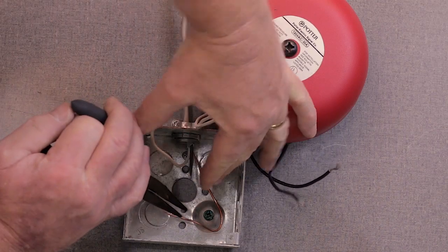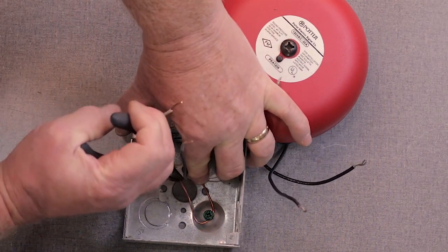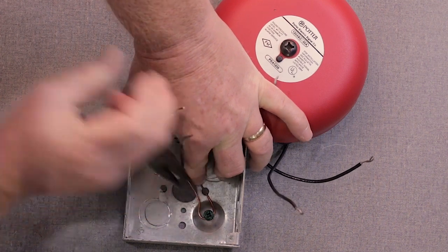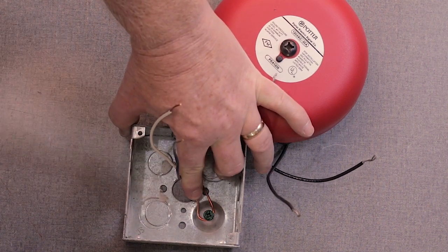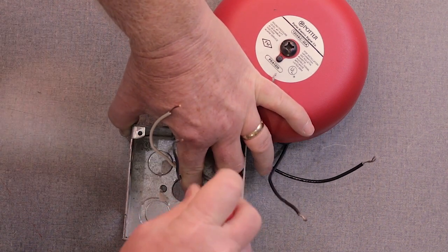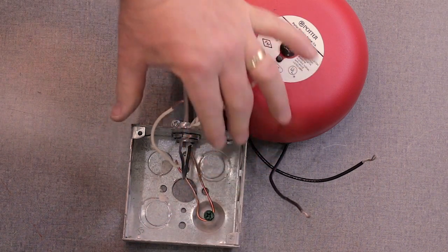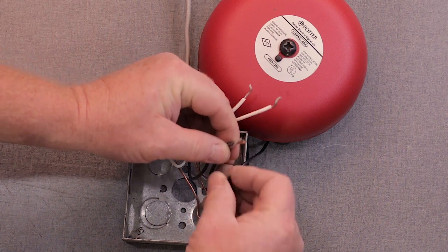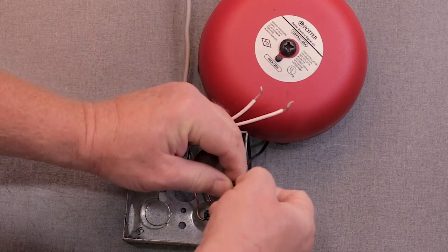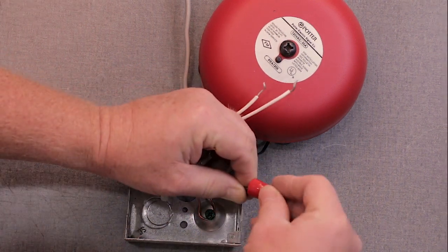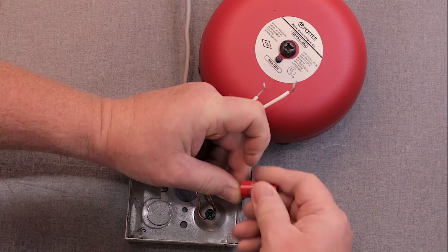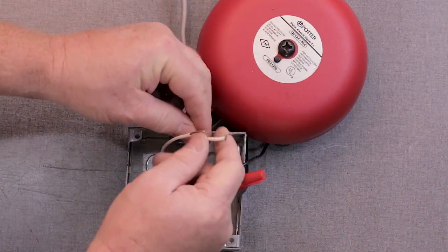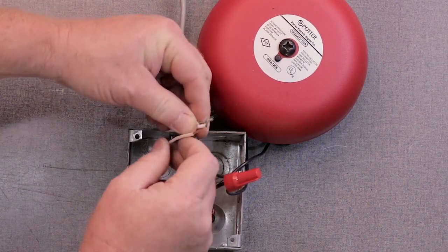Continue the ground wire from the pressure switch to the ground connection on the back box. Connect the black wire from the pressure switch to the black wires on the bell. Connect the white wire from the pressure switch to the white wires on the bell.